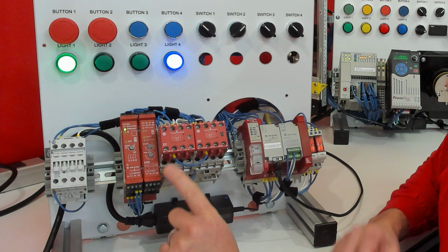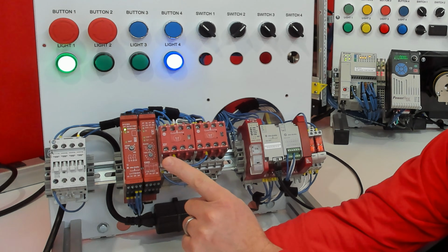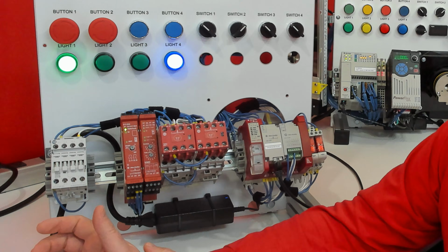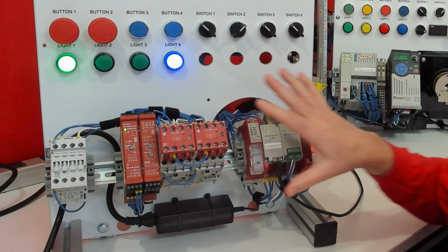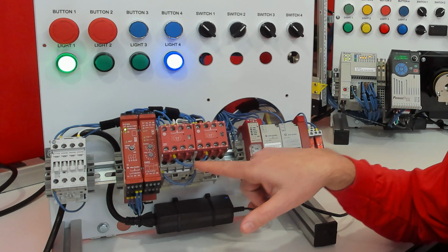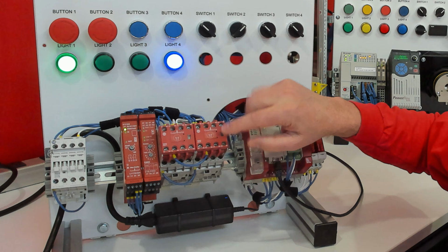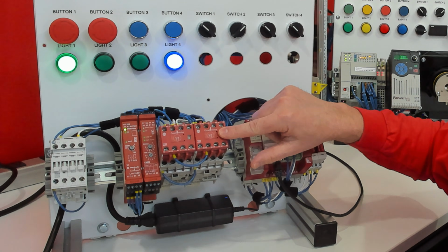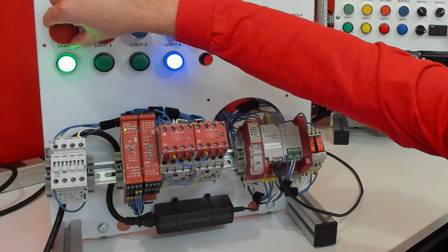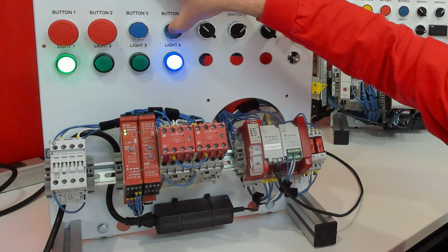Now, similarly to our e-stop failure analogy, we are back down to a single point failure with this contact welded here. And this may be the most difficult one to troubleshoot. And actually, we're going to do some videos on troubleshooting these. But the normally closed contact that you see on a lot of your safeties is a feedback, making sure that all the outputs dropped out. And if it does not have continuity through all of those, then when we pull our e-stop back out and we try to reset it, it's not going to let us reset.